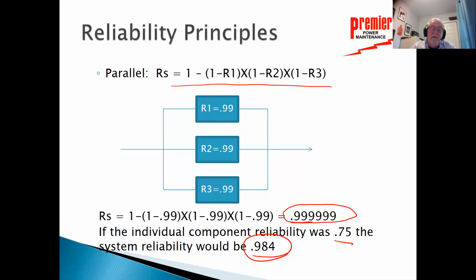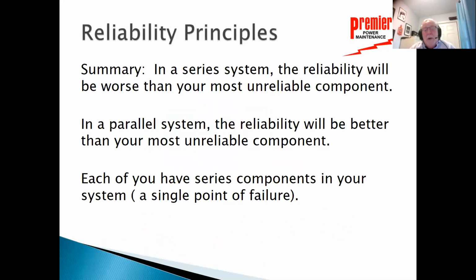So we can understand the concepts here, and we glean from that. The summary is that in a series system, the reliability is always going to be worse than your most unreliable component. In that parallel system, the reliability is going to be better than your most unreliable component. So we bring that up just so we can comprehend what we're actually looking at when we look at our own systems. Each of us have series components in our systems where we would have a single point of failure. And that's where we're going to focus a lot of our time today, talking about those situations where we would have a single point of failure that could cause us a real problem.